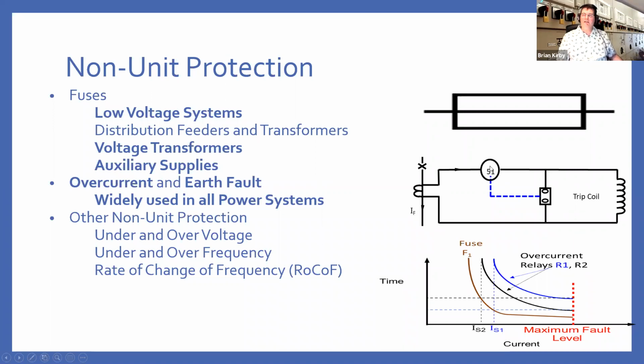51 is an ANSI designation for a time-delayed overcurrent element. So what you're doing here is you're measuring the current flow, and then you have some sort of contact and your trip coil, and you will control the energization of your trip coil.